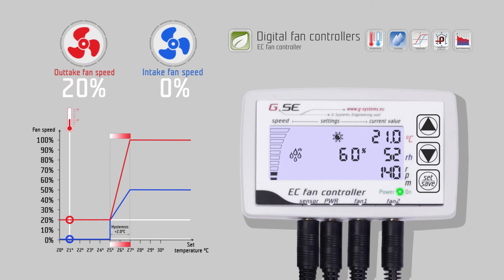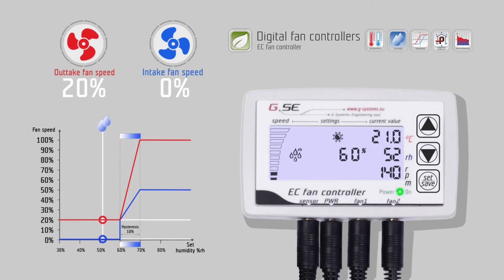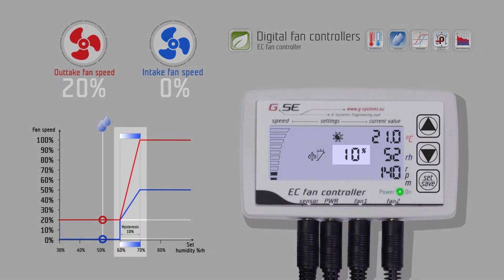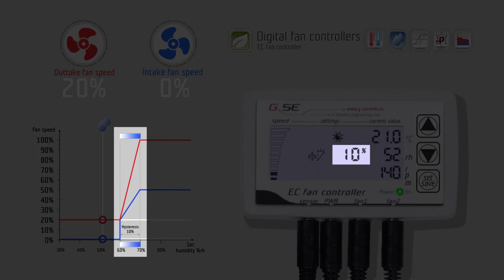Press down to go to the humidity day setting. The humidity value is set the same way as the temperature value. Press down to go to the daytime hysteresis setting for humidity. Same as temperature, the humidity hysteresis refers to the value between the lowest and the highest value of the regulation.